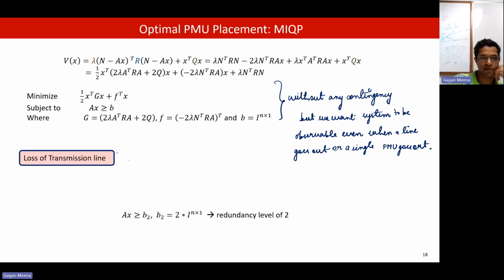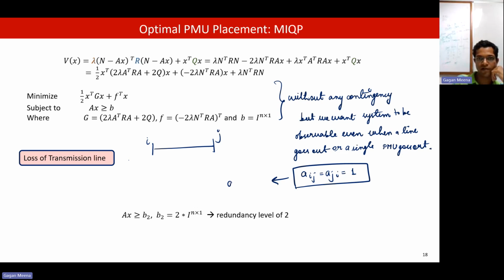These are the constraints for loss of a transmission line. If there is a transmission line between bus i and j, then in the connectivity matrix we have A_ij equals A_ji equals 1. But if you want to remove this line, we need to update A_ij, A_ji equal to 0, and the corresponding two rows A_i and A_j, multiplied with x, should be greater than or equal to 1.